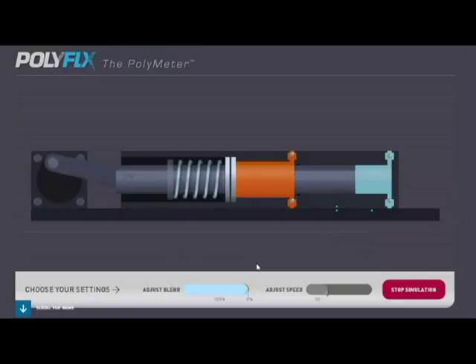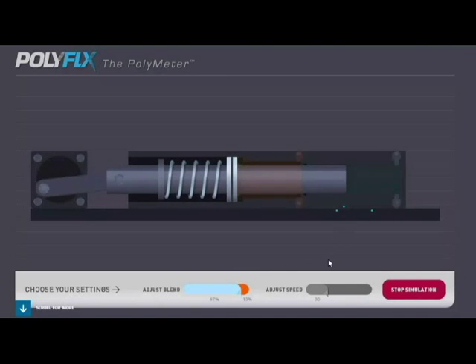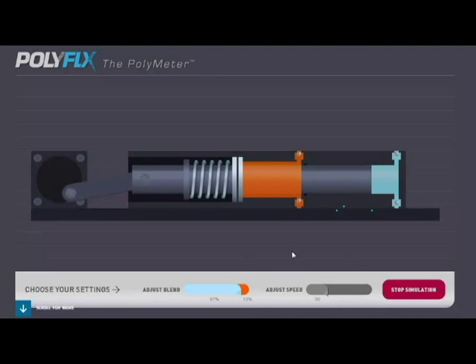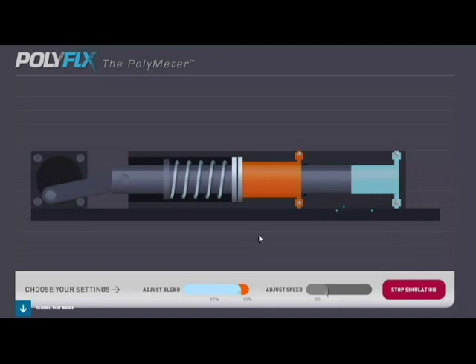If we wish to pump some of the orange liquid into the process, then we just move the slider on the simulator, thereby moving the pump housing further from the motor. The amount of blue liquid being pumped remains unchanged, but we can now see that the piston ring has started to move a little. The amount of movement is equal to 13% of the total liquid being pumped, while the blue liquid provides 87%.